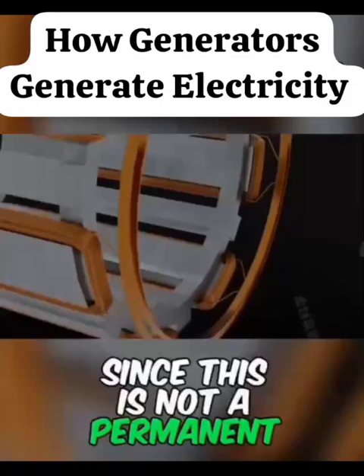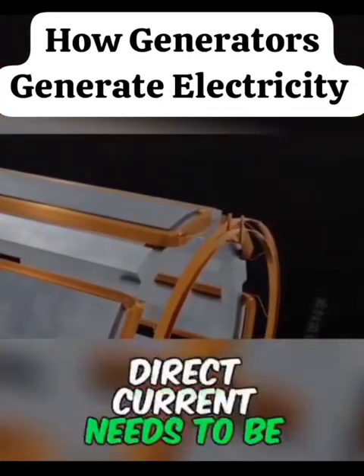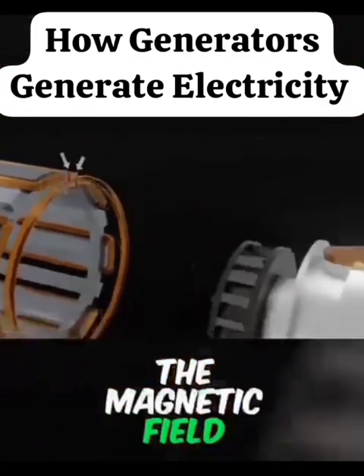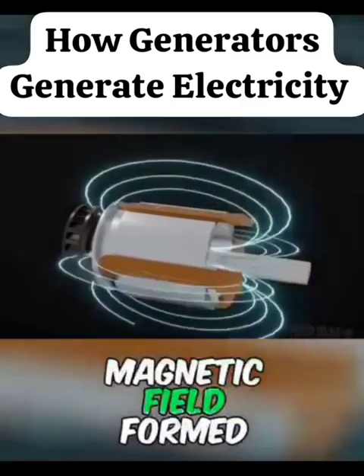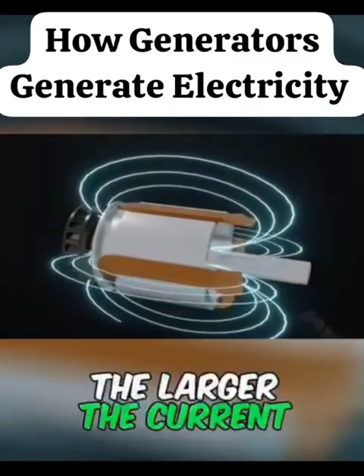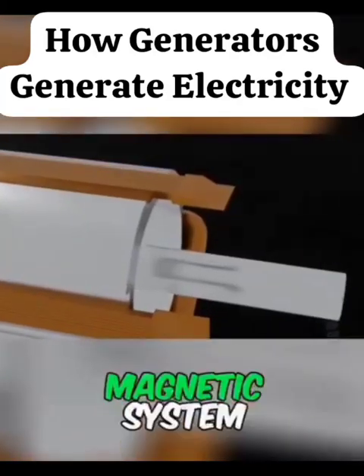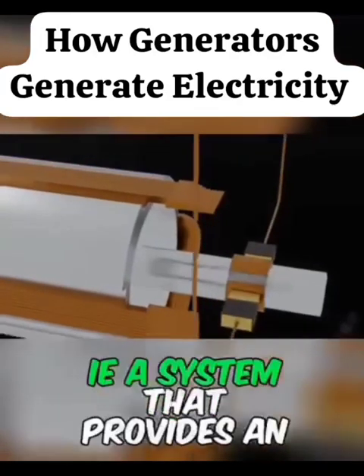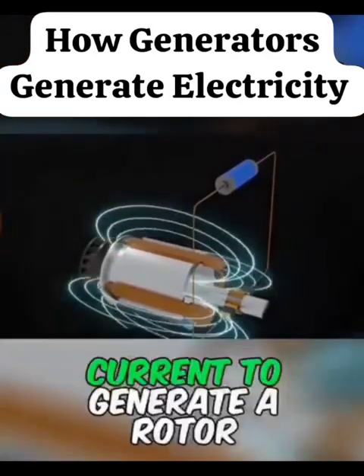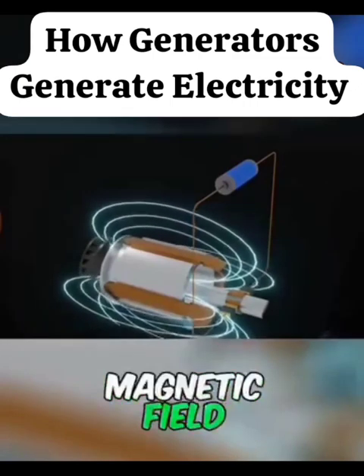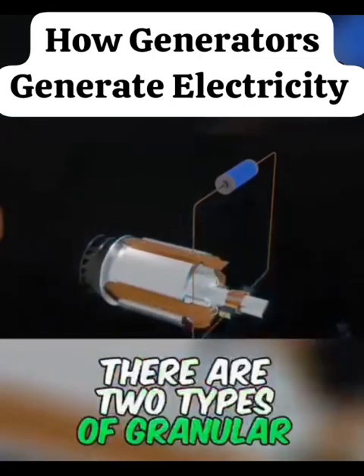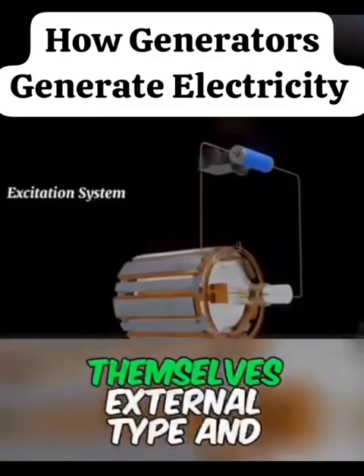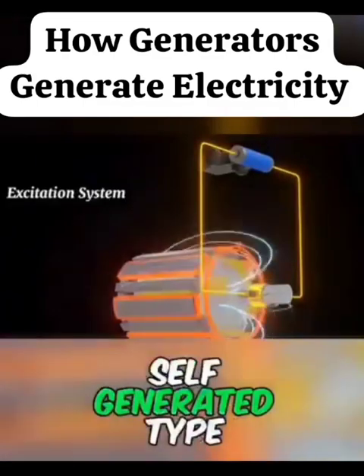Since this is not a permanent magnet, direct current needs to be passed to excite the magnetic field. The stronger the magnetic field formed, the larger the current. This is called an excitation system, i.e., a system that provides an initial current to generate a rotor magnetic field. There are two types of excitation systems themselves, external type and self-generated type.